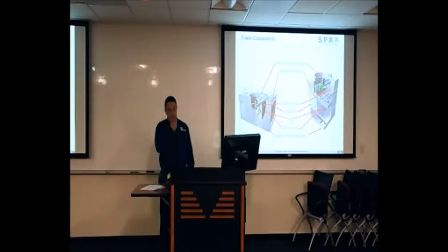Before you ever do that, I would recommend you check in with the manufacturer if they're okay with that. I know certain fans, I'm not sure what Marley's max RPM is on your gearbox. I know he asked about the minimum, because I've seen that in the past where some manufacturers have a minimum to make sure they get proper lubrication. Some of them have a maximum as well. So before you decide to increase the RPM on this thing, I would check with your manufacturer, make sure they allow for the extra RPMs. But this drive is capable of doing that.